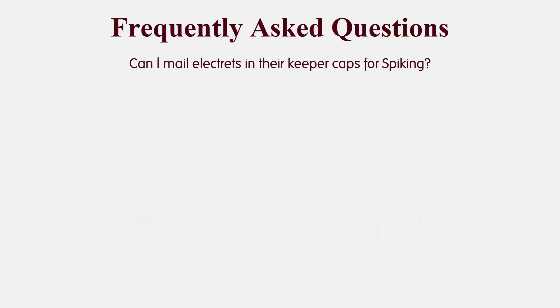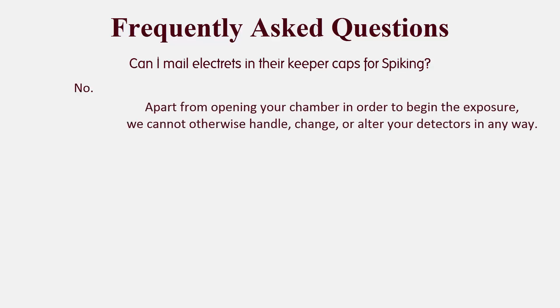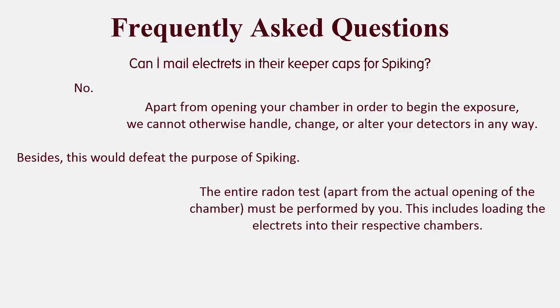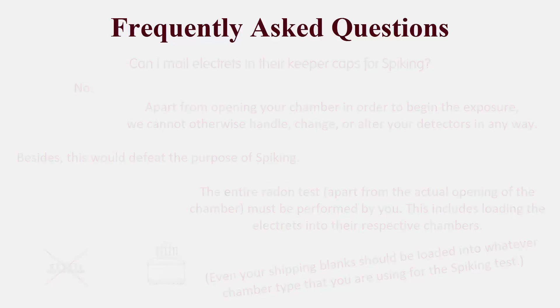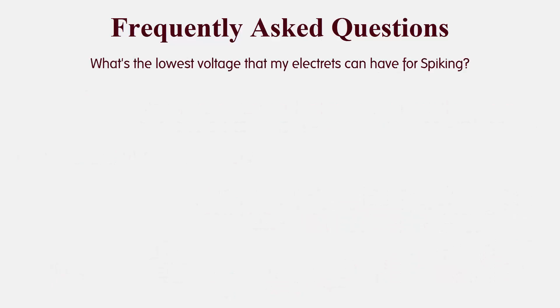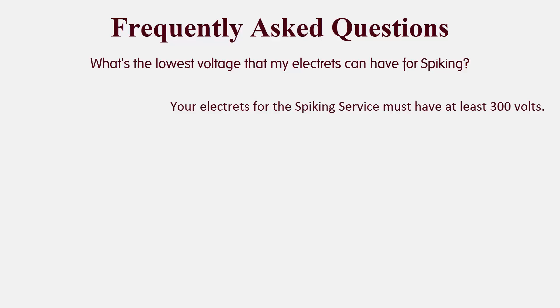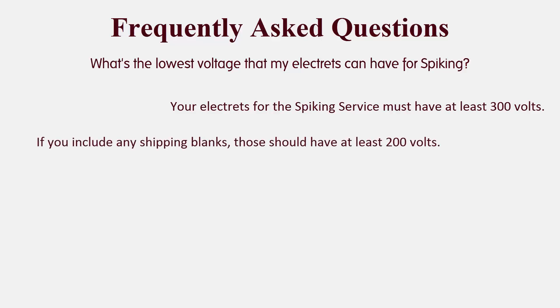Can I mail electrets in their keeper caps for spiking? The answer is no. Apart from opening your chamber in order to begin the exposure, Radelec cannot otherwise handle, change, or alter your detectors in any way. Besides, this defeats the purpose of spiking, which is to go through the entire process of performing a radon test — and this includes loading an electret into its chamber. Even your shipping blanks should be loaded into whatever chamber type you're using. What's the lowest voltage that my electrets can have for spiking? Electrets for the spiking service must have at least 300 volts. Furthermore, if you include any shipping blanks, those should have at least 200 volts.